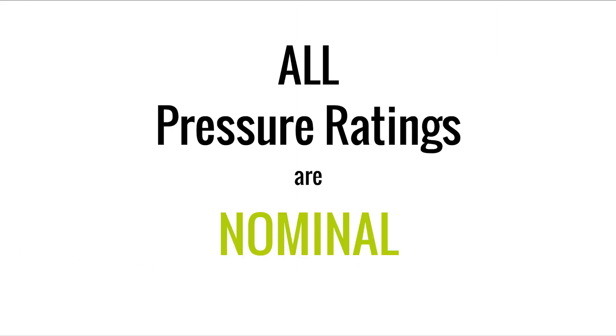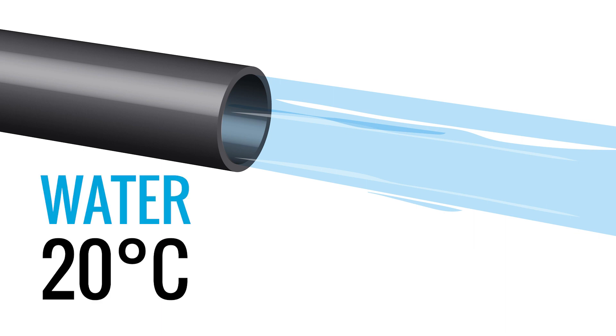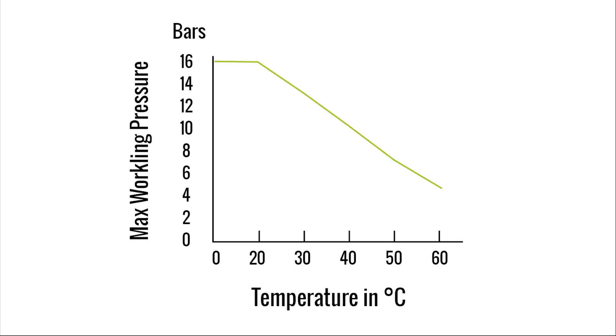The pressure handling capability of pipe is always dependent on multiple factors, and the pressure rating cannot cover all factors for every application. So it is essential to bear in mind that the pressure rating is based on piping water or similar media at a temperature of 20 degrees Celsius. Whenever piping at higher temperatures, the operating pressure should decrease — this is known as derating.